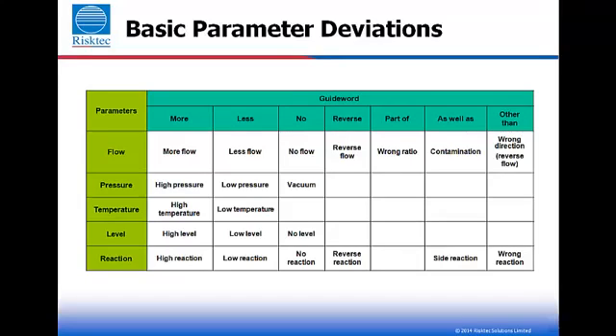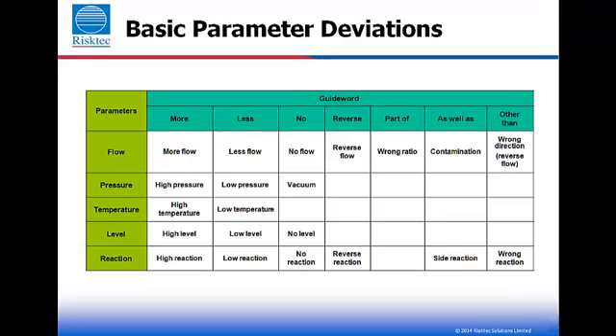Additional parameters and guide words may also be considered. For example, loss of utilities and/or services, maintenance, sampling. Different sets of guide words and deviations are used in different industries and for different situations. For example, when dealing with batch operations, guide words relating to the sequencing of an operation are important. For control systems, we could be thinking about the frequency or amplitude of a signal, interference and noise levels.